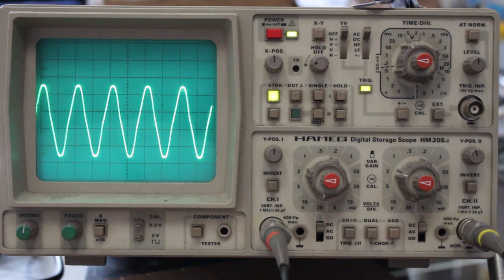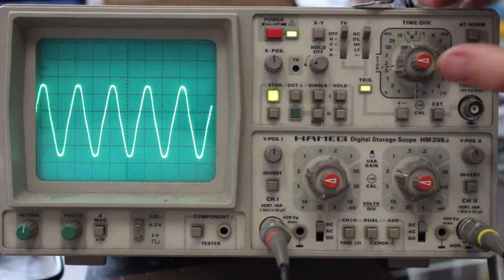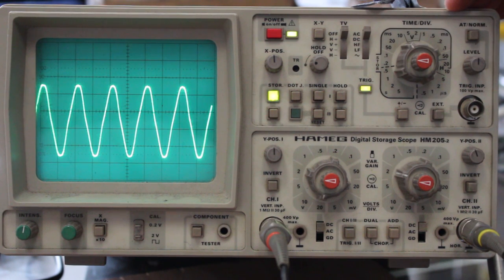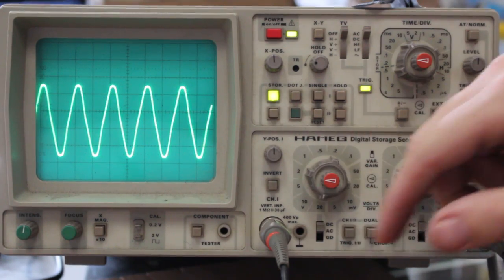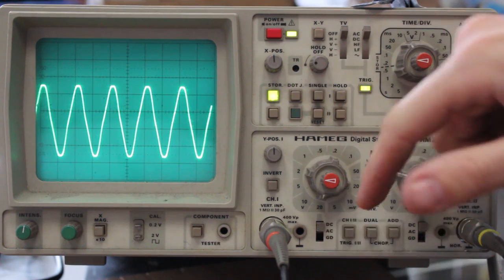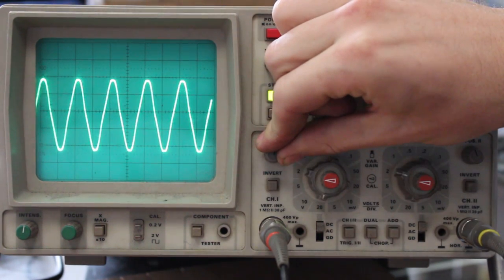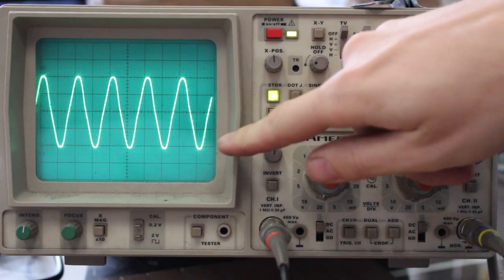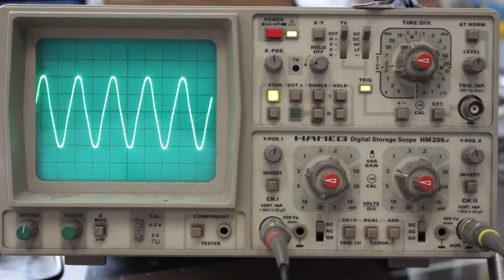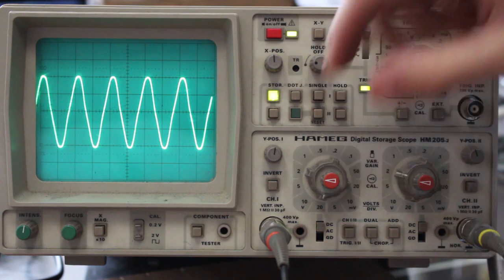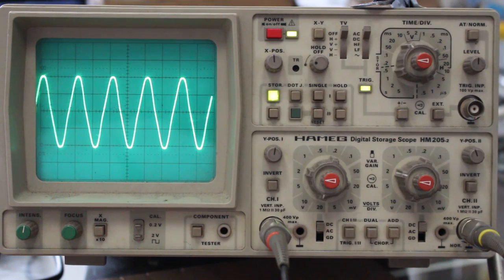So going back to our signal, which is from a 24 volt AC transformer, let's see if it really is 24 volts AC. We're at the moment set to 20 volts per centimetre. And if I just align this, so it's easier to count the divisions, we've got 4 divisions peak to peak. So that's 80 volts peak to peak. That sounds a bit suspicious for a 24 volt AC transformer, because that would mean that we've got 40 volts on each oscillation of the waveform.